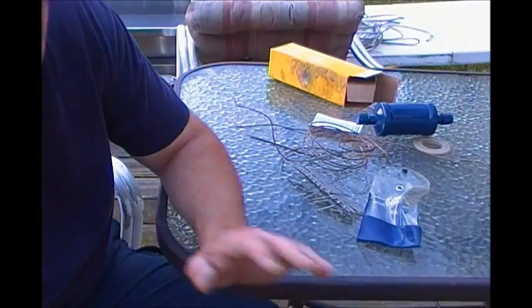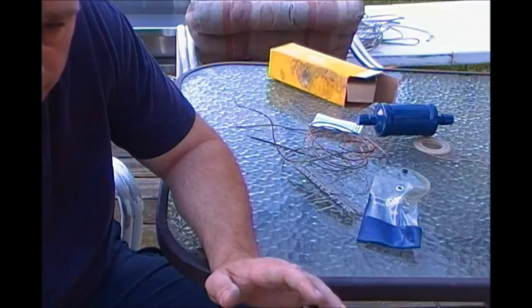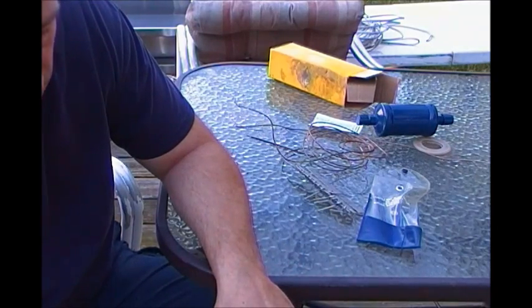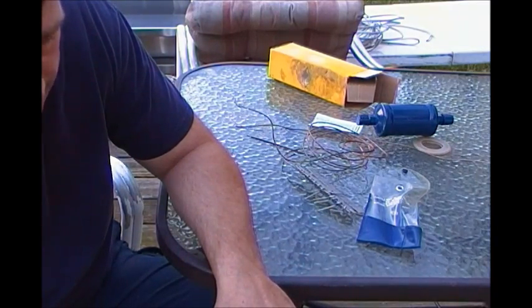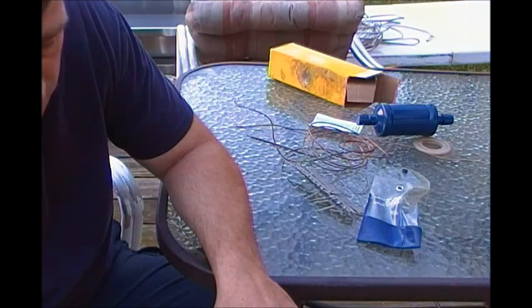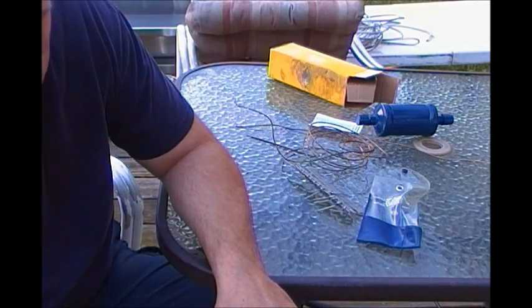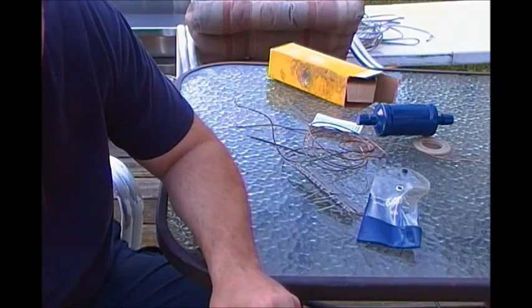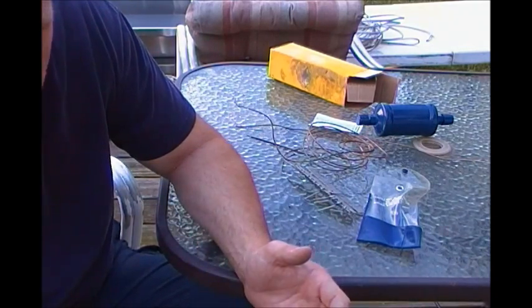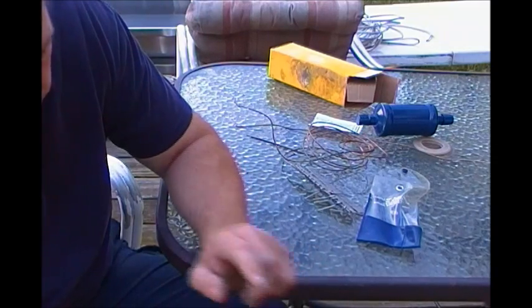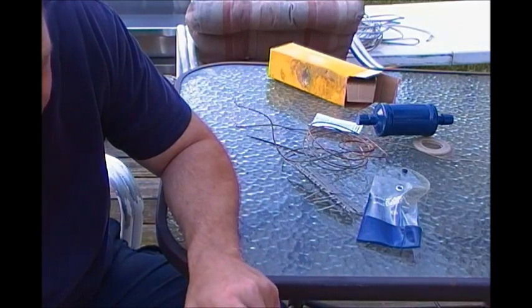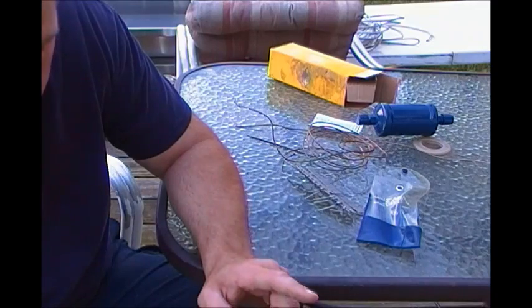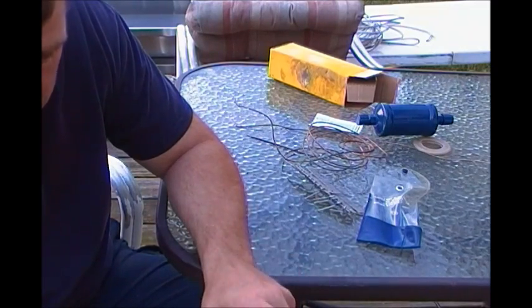Well, here's how you do it. They got a little chart inside of the capillary tube. It tells you what horsepower and what gas type you're using, what the diameter should be and how long the capillary should be. So how do you determine that? You take the number off the compressor. You get yourself a little Copeland handbook. You open it up. You find the model number on the compressor. It will tell you what horsepower the compressor is.